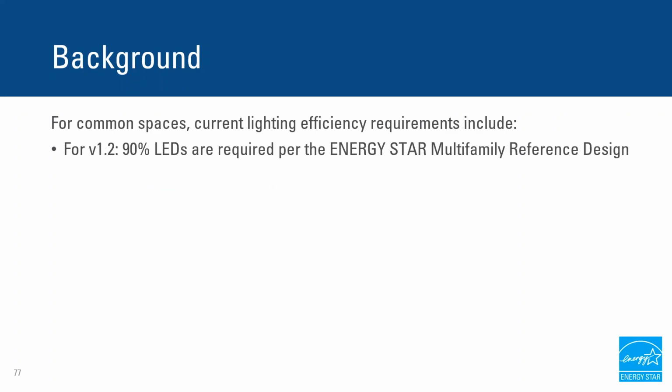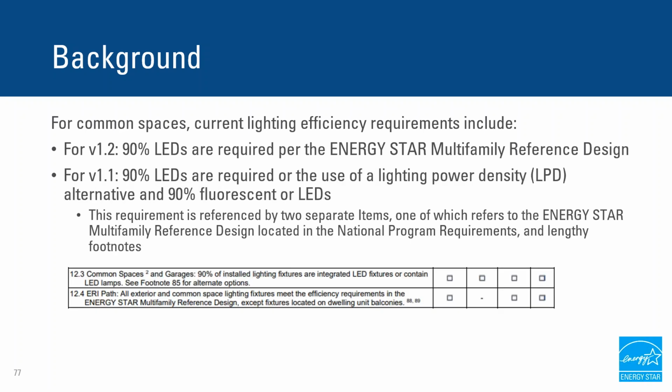For background, in common spaces, current lighting efficiency requirements include 90% LEDs, which are required based on the Multifamily Reference Design for the ERI path and prescriptive path. And then for version 1.1, 90% LEDs are required for the lighting power density, or you can use a lighting power density alternative and 90% fluorescent lighting or LEDs.